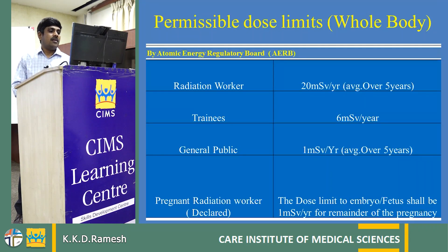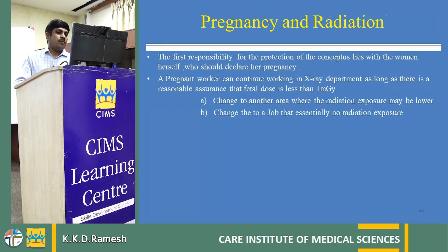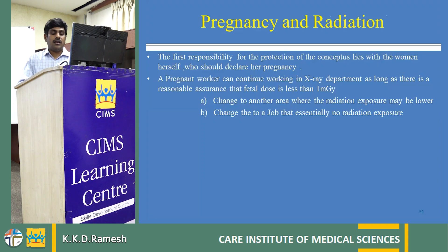Safe dose limits of radiation are provided by AERB. For radiation workers, the dose limit is 20 millisieverts per year averaged over five years. For trainees, the dose limit is 6 millisieverts per year. For the general public, it is 1 millisievert per year. For pregnant radiation workers, the dose limit is 1 millisievert per year, as the embryo or fetus is considered general public. It is the responsibility of the female radiation worker to declare her pregnancy and convey the message to the HOD and the local Radiation Safety Committee.